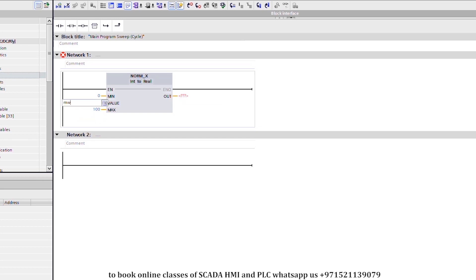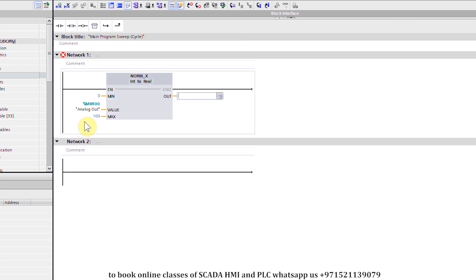In the value we will write Memory Word 100, which is our input word. Memory Word 100 will be used to generate the analog output. The values of Memory Word 100 will be taken between zero to one hundred and normalized between 0.0 to 1.0, and the result will be saved in the output.